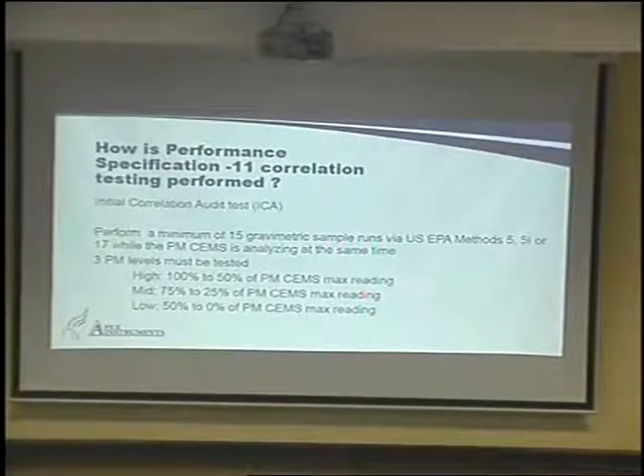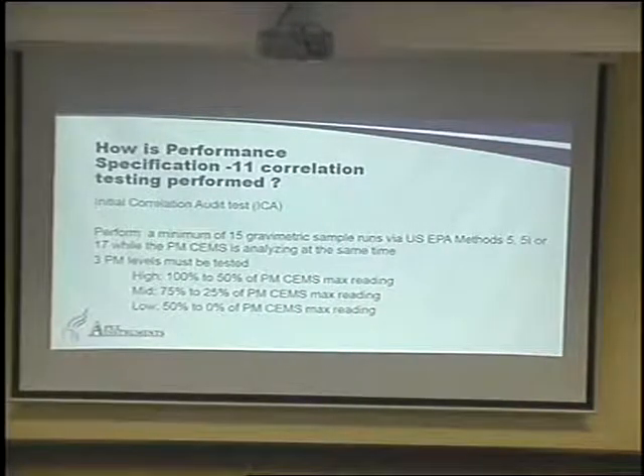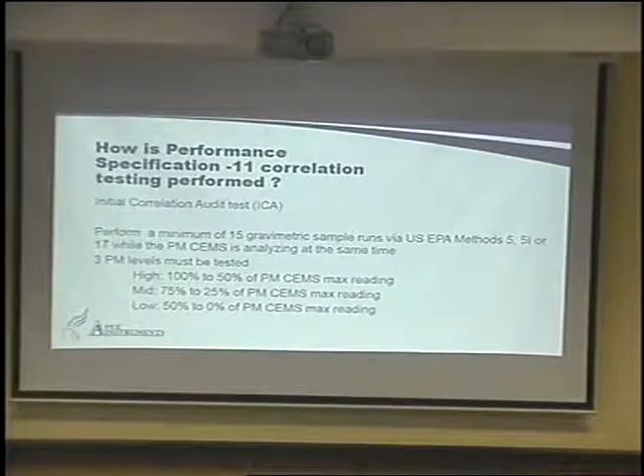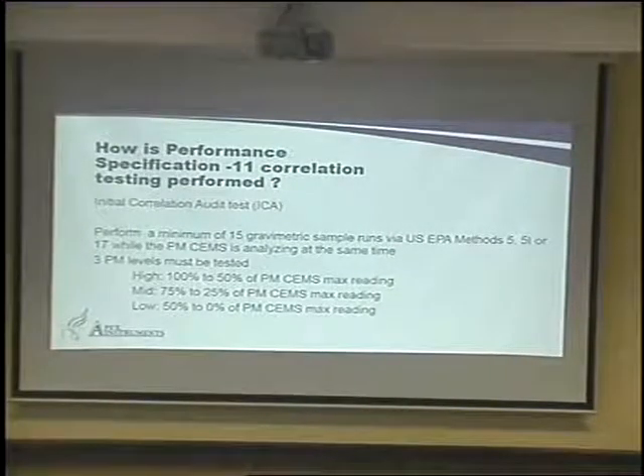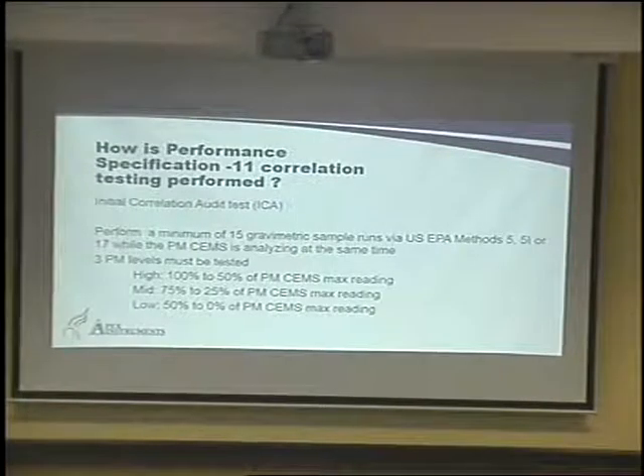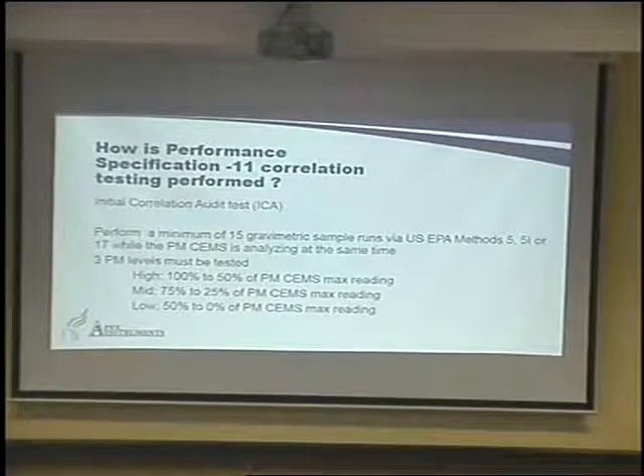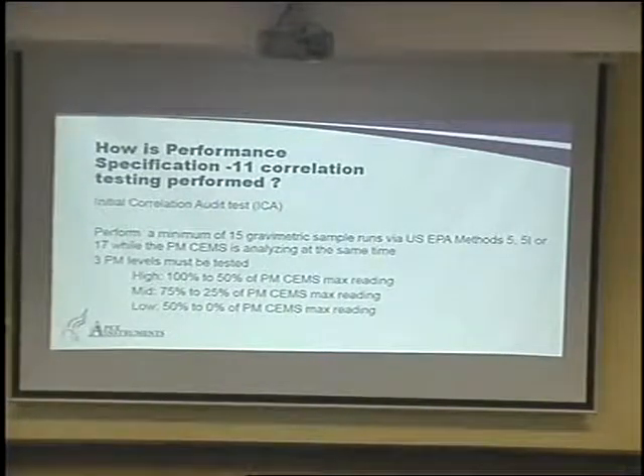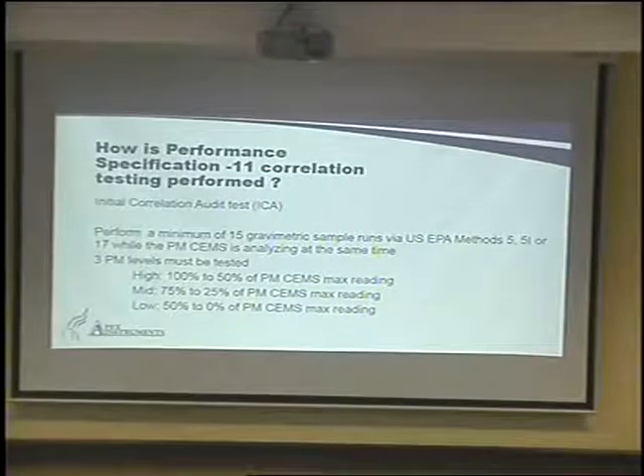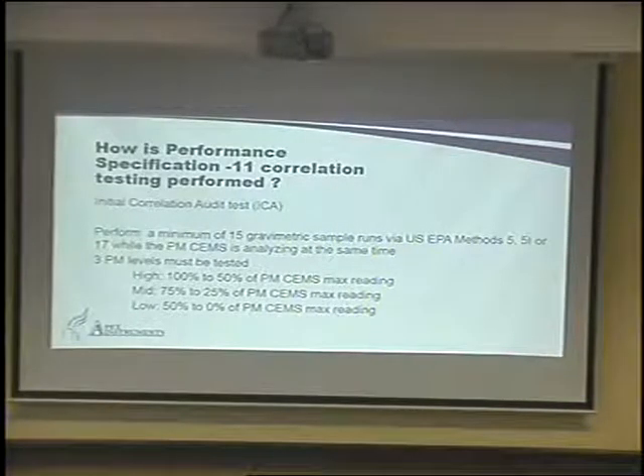Process monitoring is another application. If a PM CEMS is running normally and then suddenly spikes, we have a problem. Maybe the process changed, maybe a bag broke in the bag house, the ESP isn't working correctly, or we got raw material for our boiler from a different source — coal from Colombia instead of Indonesia, causing a change in emission rate. With this instrument reporting accurately, we can start making decisions about what may have changed.